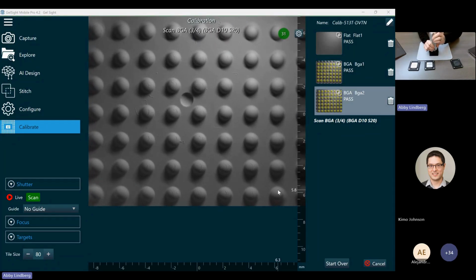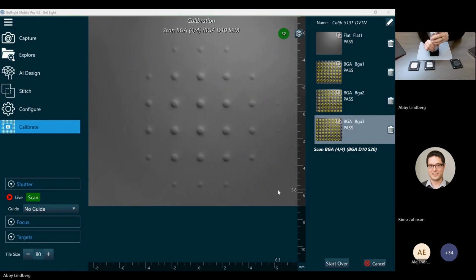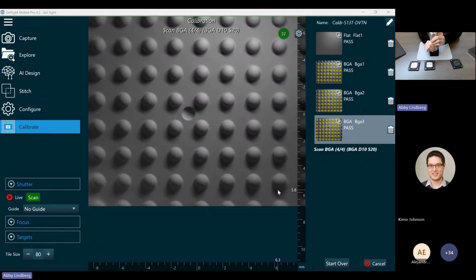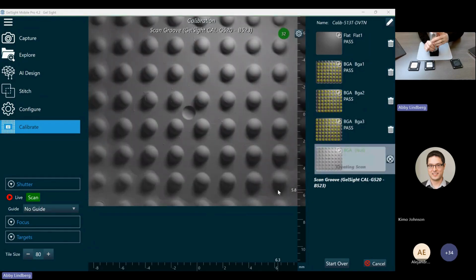And we use that as a visual indication that you're applying enough force to see the gel conform around the spheres. If that's about 25 to 50% covered with a shadow, you're pressing down hard enough for the gel to conform. And you'll see on the right-hand side, we draw a bunch of yellow circles around those spheres when they're found by the algorithm.